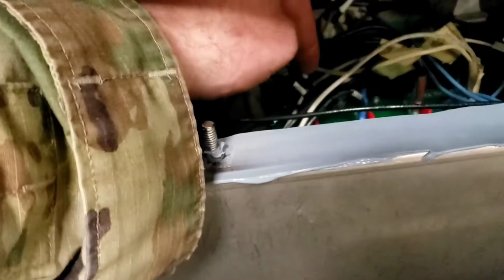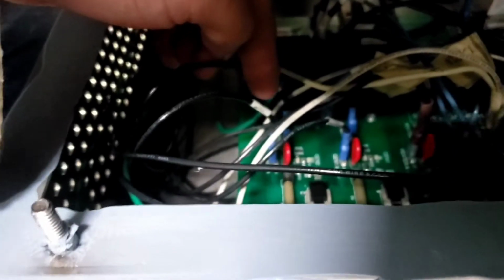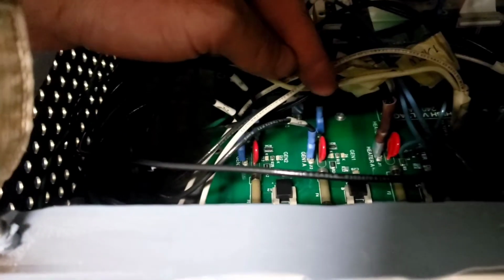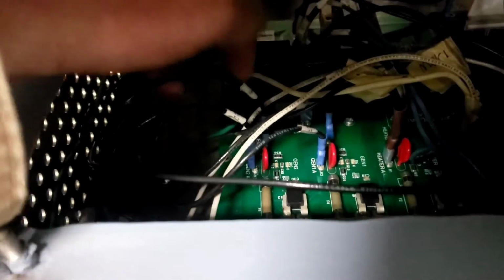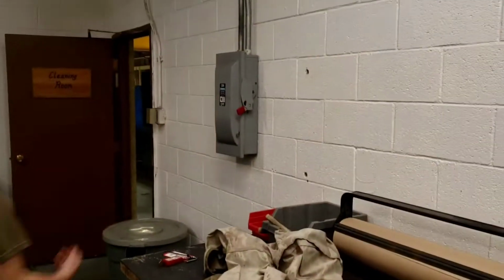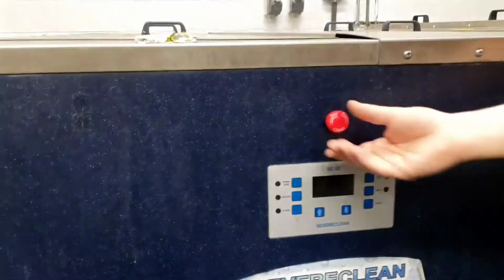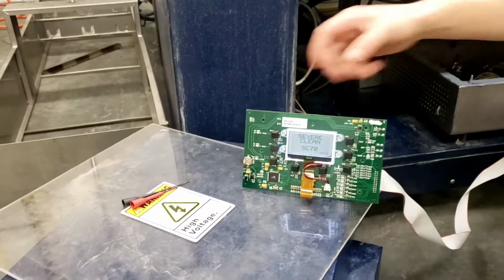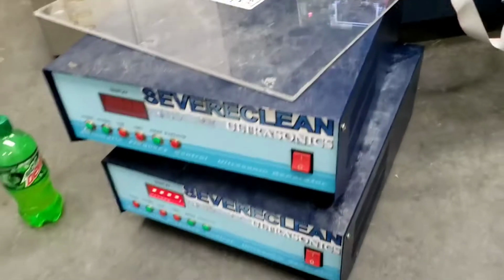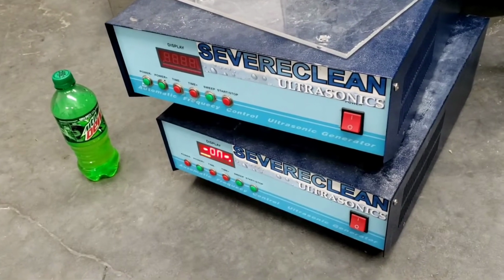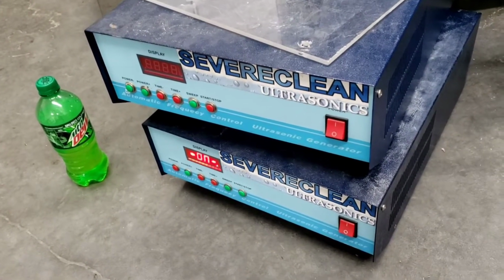Alrighty, so what we did there is he swapped Gen 2 to Gen 1. Sorry, it's hard to see in here. He swapped these two wires, moved them over here, and these two moved them over here. So now we're going to turn on the circuit breaker again. Go ahead and turn on the main board, which turns that on. You hit power, and now the bottom one works as before and the top one works, which is expected. That tells us that that board is good.